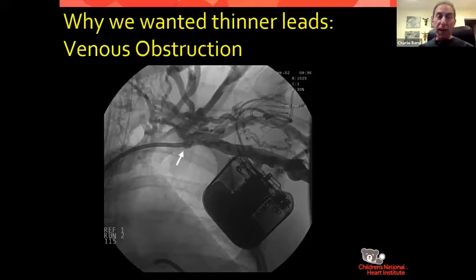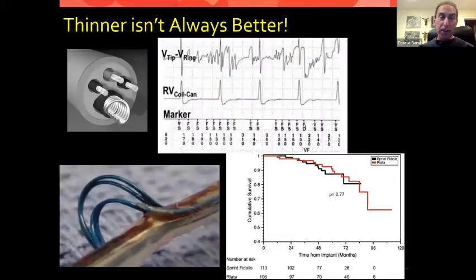So we have pleaded with the companies to make thinner leads, which they did. But then we learned the hard way that thinner isn't always better. On the top, there's two ways to make the leads thinner. One is to put less insulation, the polyurethane and silicone, between the conductors. So if you put less insulation between them, the leads can be thinner. But it turned out that in this situation, there became electrical noise that we saw on the leads. And the defibrillator saw that noise as possibly a ventricular arrhythmia and caused inappropriate shocks.